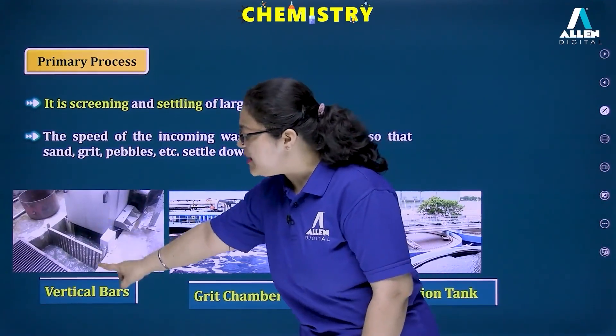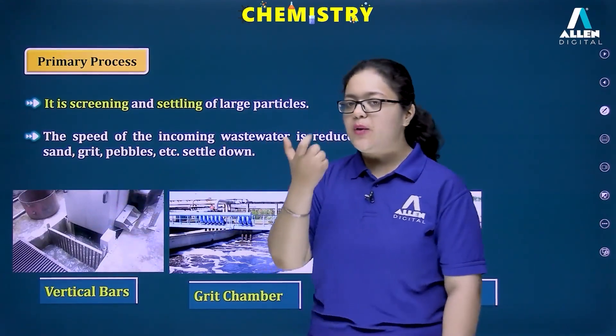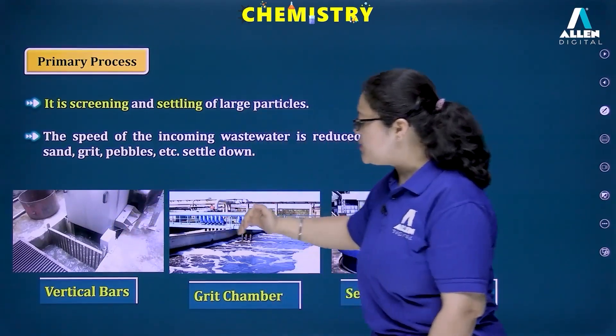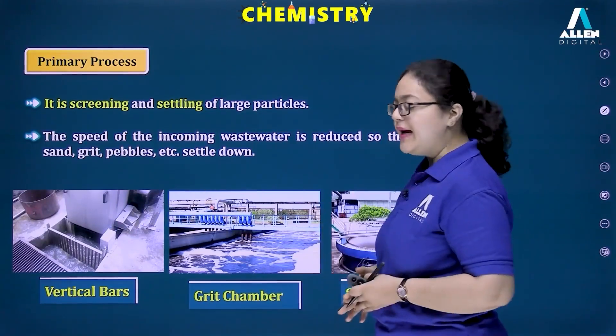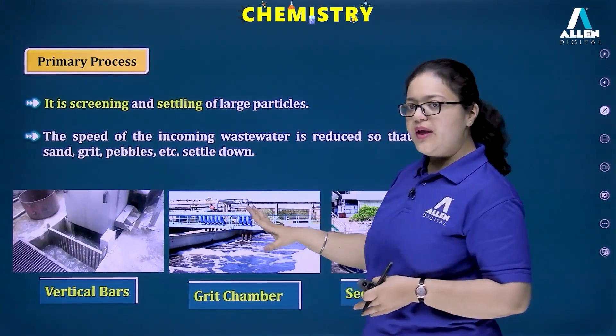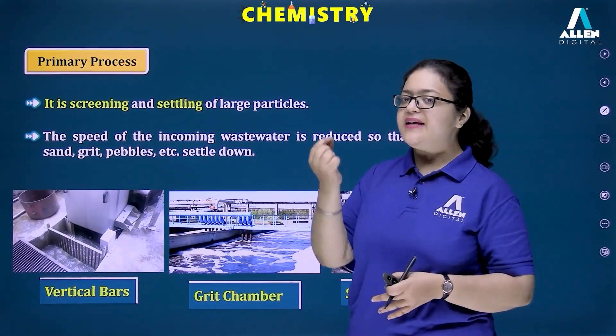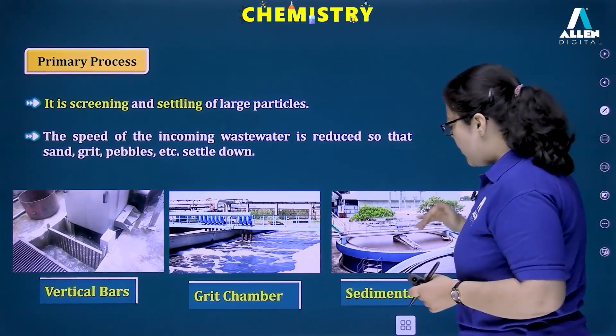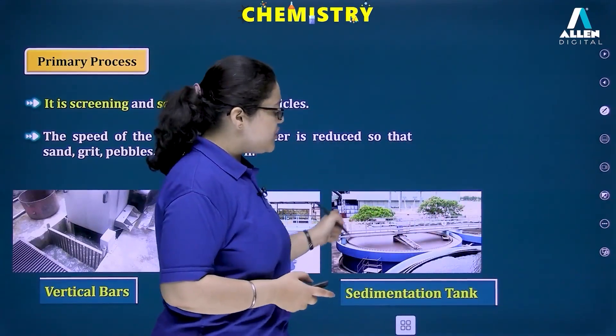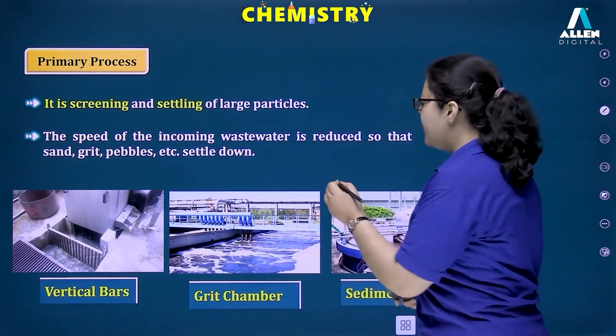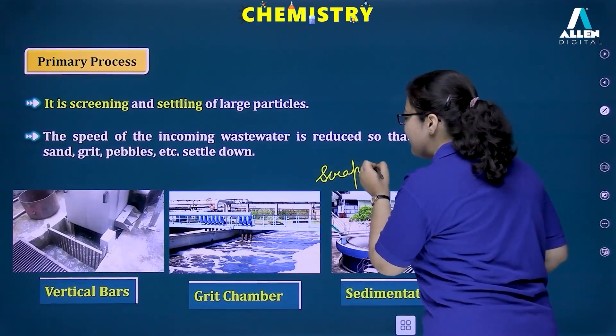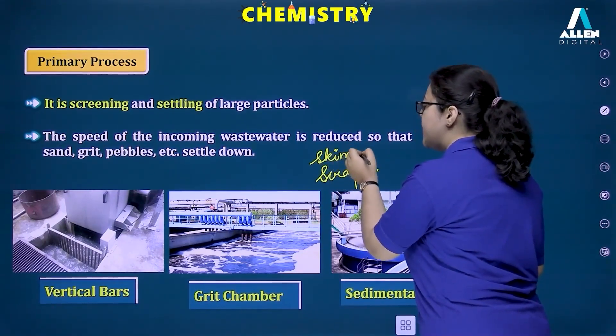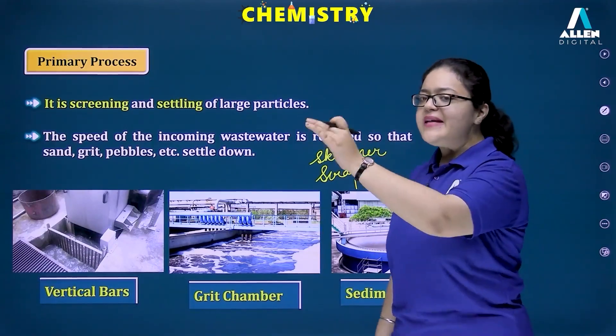The primary process has three steps. First, vertical metal bars — closely spaced — block and remove impurities like plastic, wood, cloths, rags, and sticks. Then the wastewater is drawn into the grit chamber, a narrow rectangular tank, where sand, grit, silt, and mud particles settle down. It is then drawn into the sedimentation tank, where organic impurities settle as sludge removed by a scraper, and light floatable impurities like oil and grease are removed by a skimmer. Clarified water then moves to the secondary process.